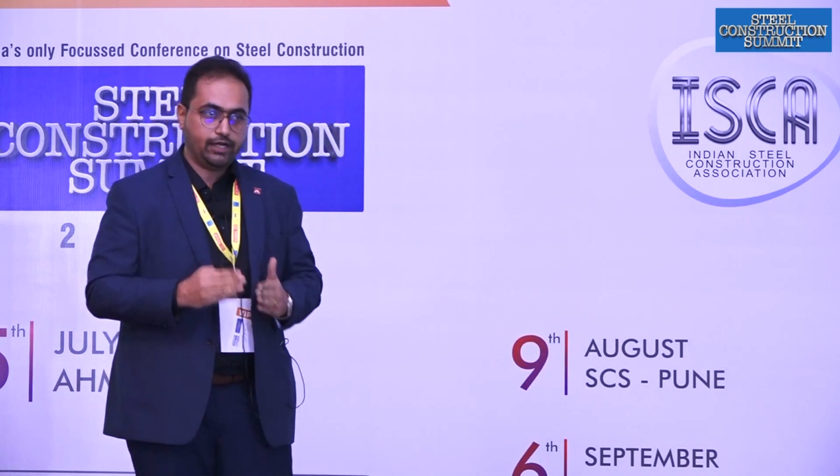So again, when you're choosing for fire resilience, what are all the factors you have to look out for? If you can see, EN 13501 fire classification is a very important and the most stringent fire classification there is today. They classify each material as per their burning characteristics. So there is class A1, class A2, which is non-combustible, and surface spread of flame and fire propagation is 0. These are the things you can check.